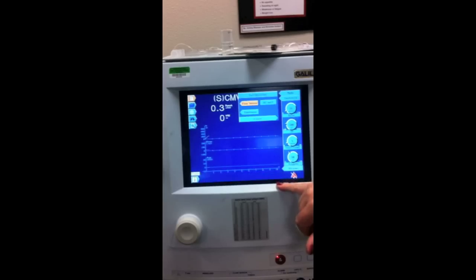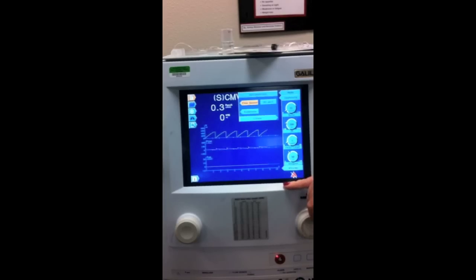And then if you don't pay attention, you'll miss it like I did, because it says it quickly and then it goes away. You need to see that it says flow sensor cal okay to know that you need to go on. If you don't see it, you need to do it again. Okay, so that's good. So we know that's done. Now we're going to go to the tightness test.